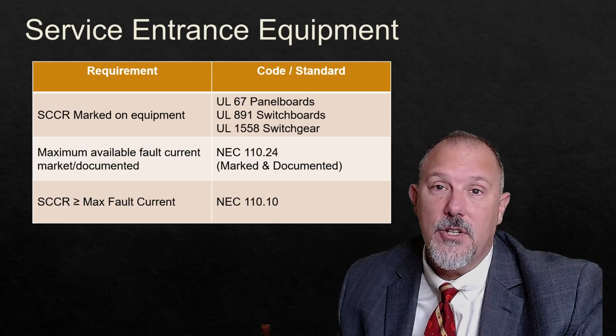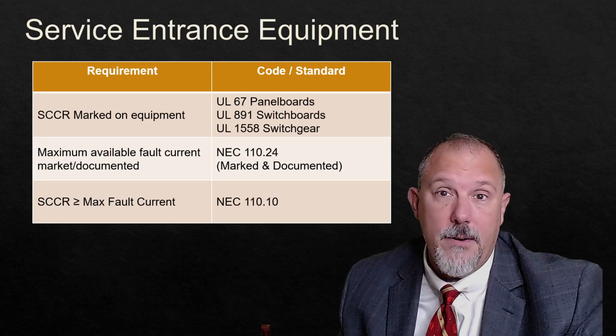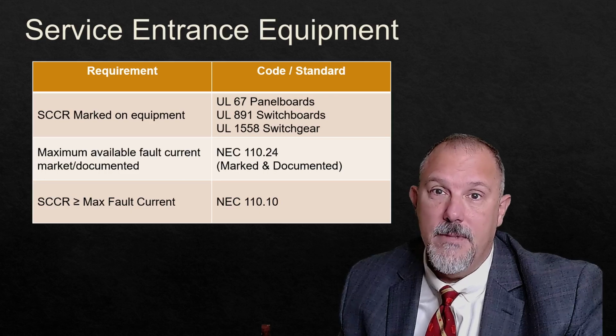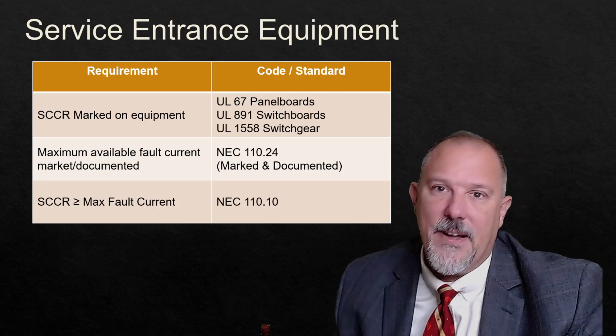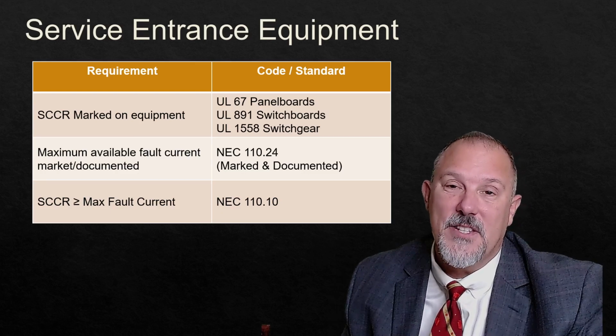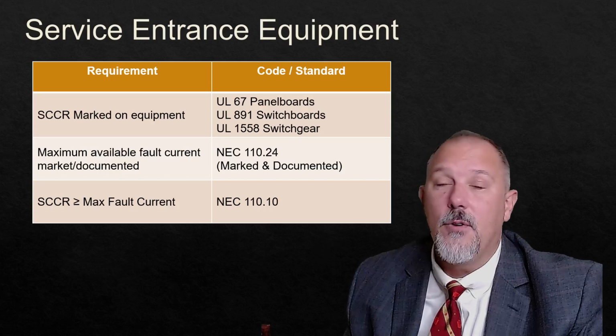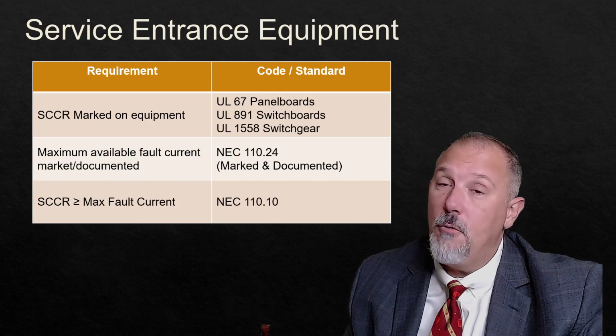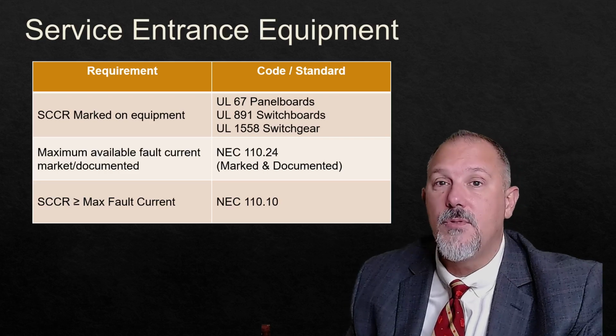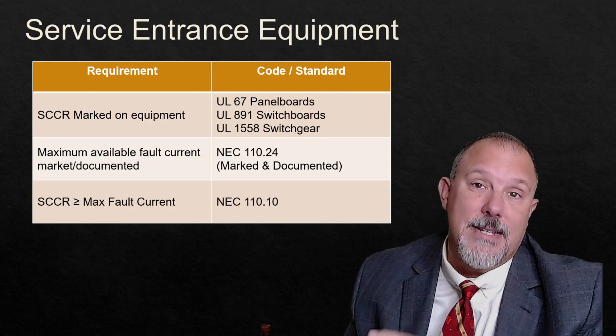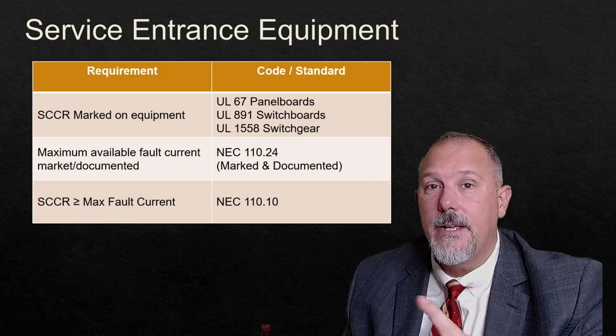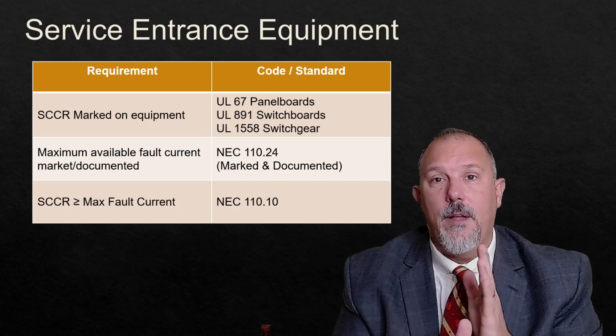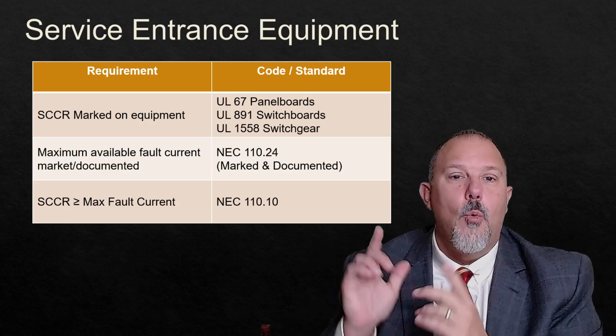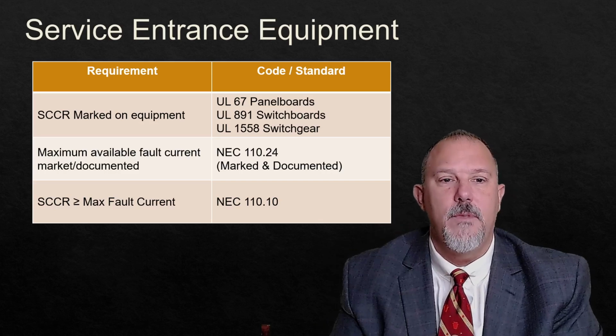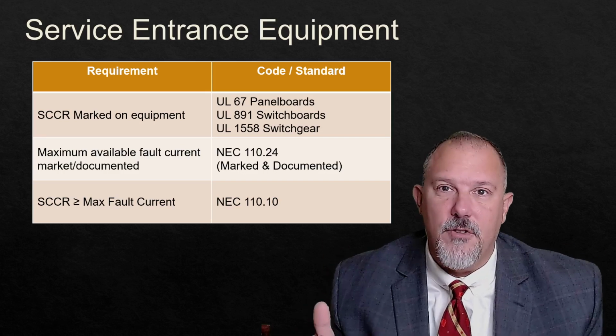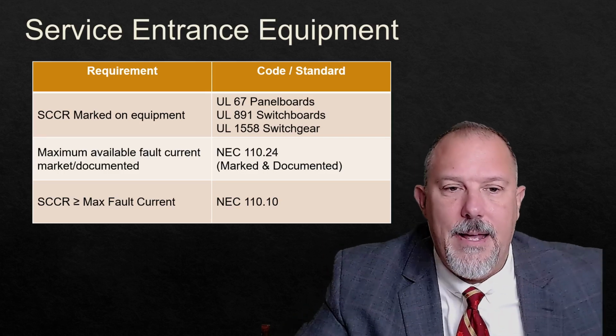Do you think the supply house is going to give you a 65K breaker when they can give you a 10K breaker? I highly doubt it. Unless you say, oh, and by the way, I need a 65K breaker because the short circuit current rating of this equipment has to be 65,000 amps. Then they'll give you that rating. But if you put a 10K breaker in that panel board, it becomes a 10,000 amp short circuit current rating for the entire panel board. One weak link can hurt you. So be mindful when you replace overcurrent devices inside of a panel board.